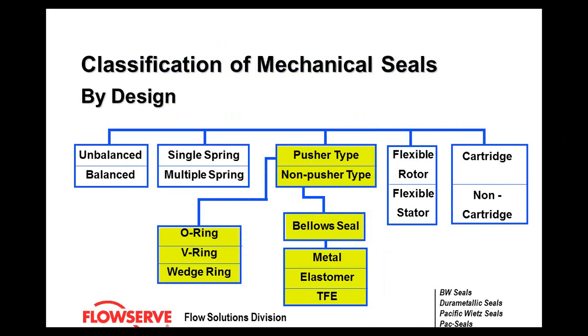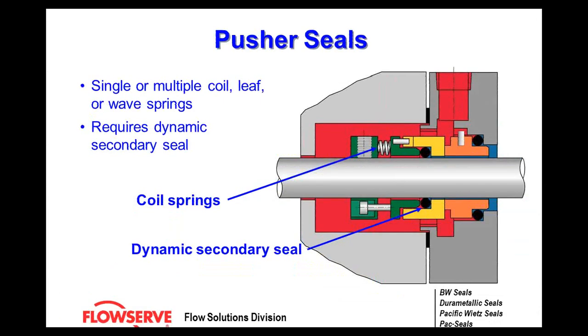Now, the differences between a pusher and a non-pusher seal. Going back to the dynamic secondary sealing area — any time you have a mechanical seal with a spring of any sort (multiple springs, single springs, leaf springs, wave springs) combined with a dynamic secondary seal and dynamic o-ring, that is a pusher seal. Pusher seals are one of the most common types.